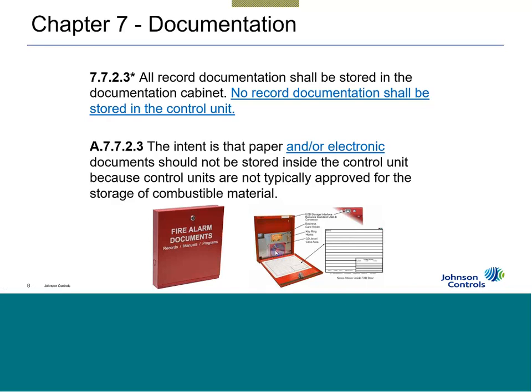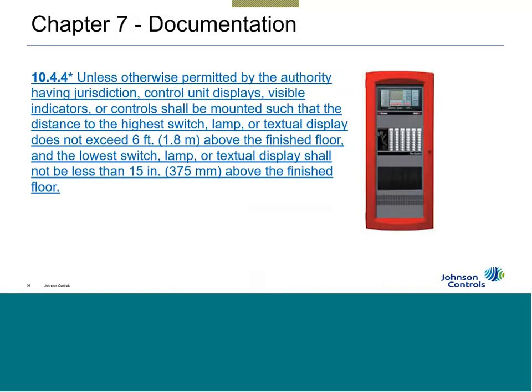Now for Johnson Controls, the Autocall 4100, for example, we have that memory card built onto the CPU. Yes, that is an acceptable way for you to store digitally your O&M manuals, your shop drawings, your data sheets, test and inspect documents if you scan them in and make them into a PDF. That is an acceptable way of doing that. So it's another option that you have.